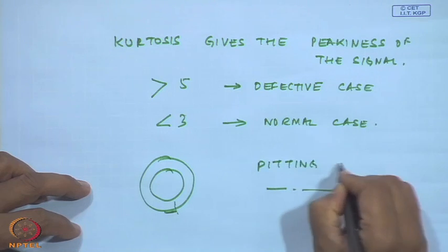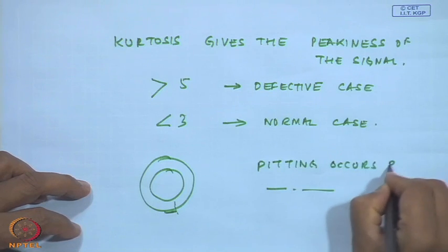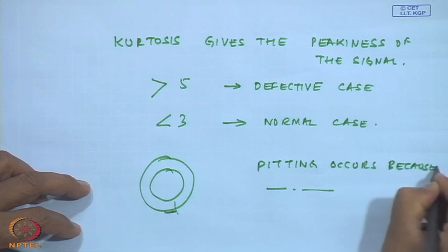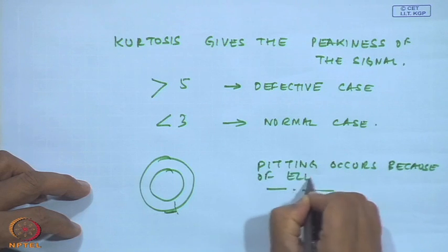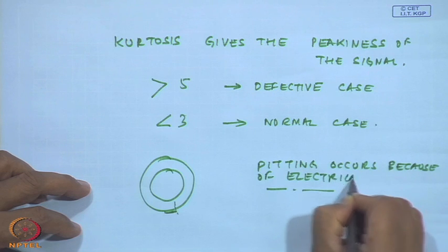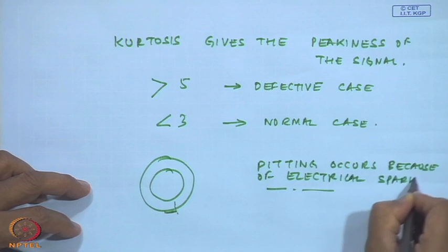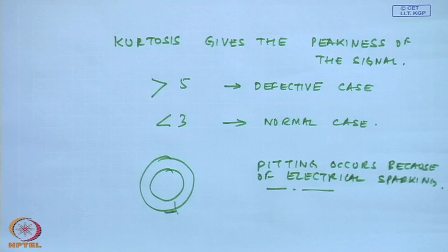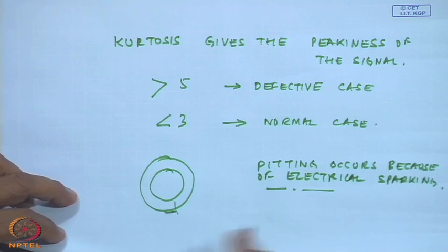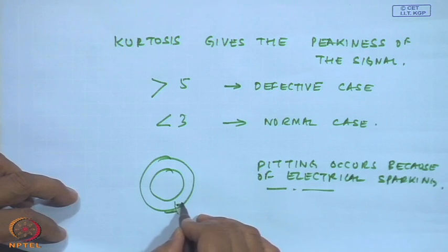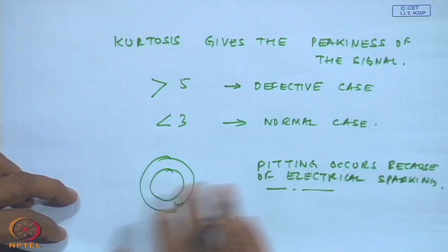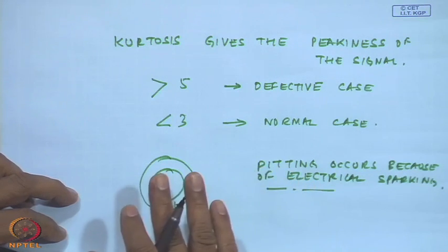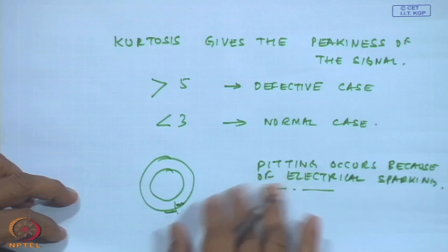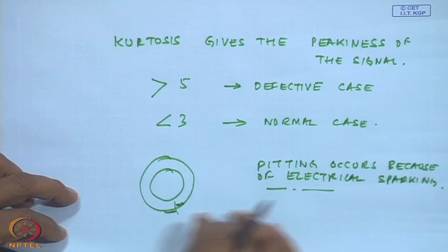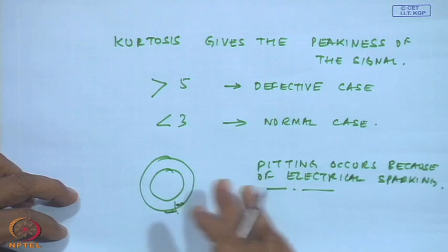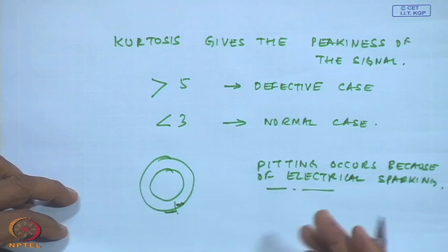Pitting occurs because of electrical sparking. So this is going to give rise to the initiation of these defects. Okay. So a good bearing has to be lubricated, kept in a dirt free environment, with care that dirt does not enter, and you also should not overload the bearing more than it was designed for.